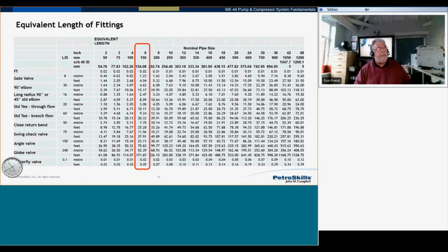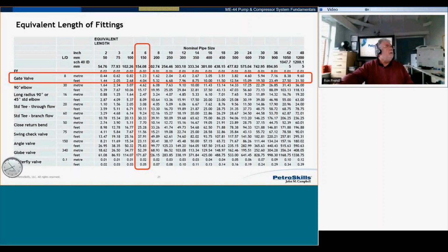Now, we could go a little bit deeper. Don't get too scared on this, guys. All I've done here is I've taken those L over D values for those different fittings, and I've applied it to different nominal size pipe. And here I'm looking at a 6-inch line. If I'm looking at a gate valve, one 6-inch gate valve gives me 1.23 meters equivalence. What that means is a 6-inch gate valve will give me the same amount of friction loss as 1.23 meters of straight pipe. So if I know what all my fittings are and I calculate the equivalent length, all I then have to do is add up all those equivalents to the actual length and then go through the same Darcy formula. Now, we're going to do one with a 4-inch pipe.